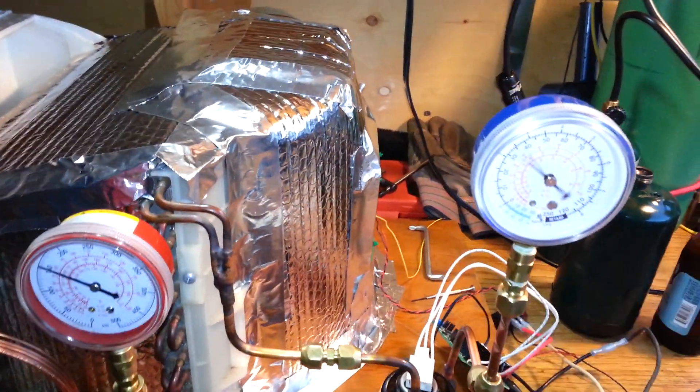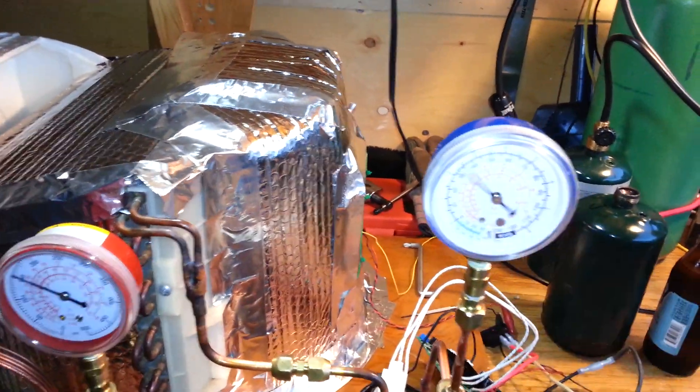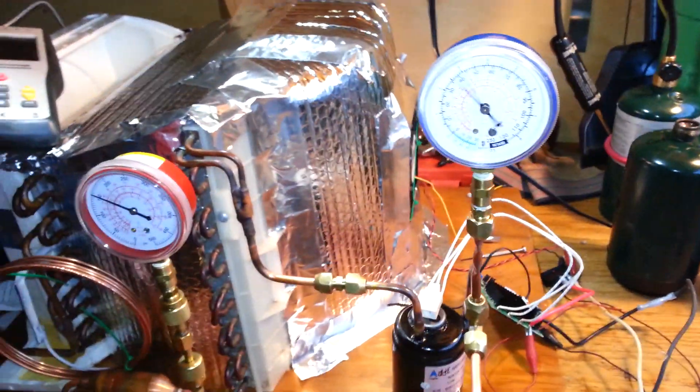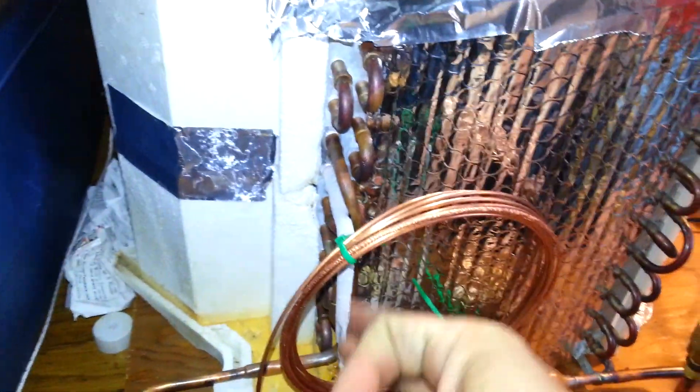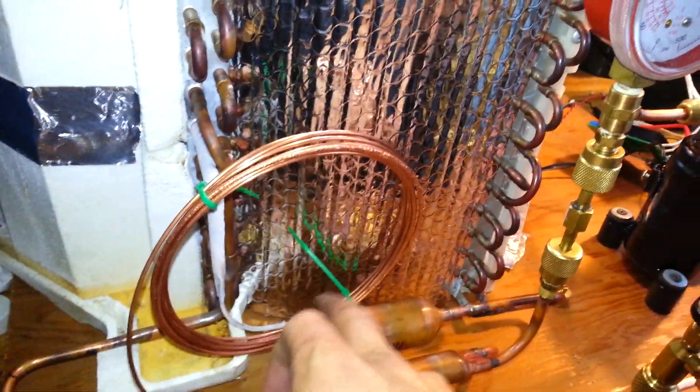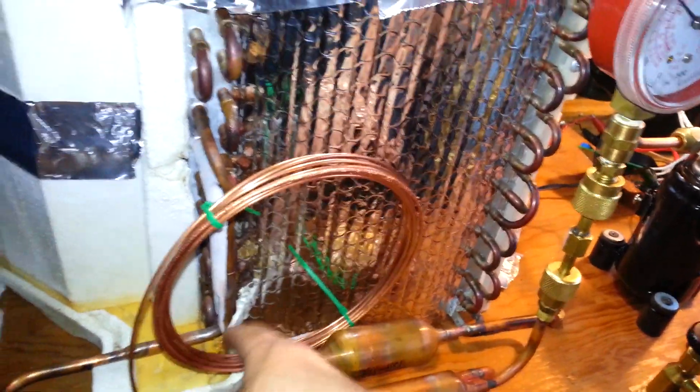Right now we're at about 35 psi, which associates to somewhere around 14, 15 degrees Fahrenheit. So it's way too cold. You can see it's frosted up right after the cap tube there. And it's condensing across the cap tube and it's frosting up.